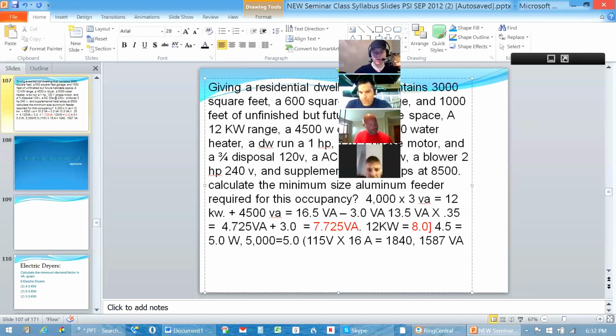Now, if the answer blocks are pretty far apart, then it's not necessary because you're going to get close enough to your answer that it won't make a huge difference. But if they're pretty close, you want to be specific with it. But the last one's going to be that 2 horsepower, 230 volts, I think it was, for the air conditioner. Air conditioner is going to be kind of a special case, but that blower motor is just a motor load. So 2 horsepower, 240 volt would give us a value of 12 amps at 230 volts. So 12 times 230 leaves us 2760 for that one. So those 3 motor loads are in that order.